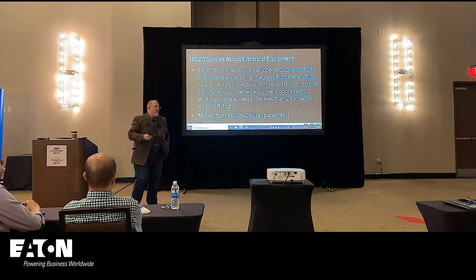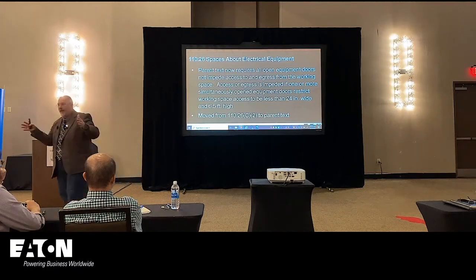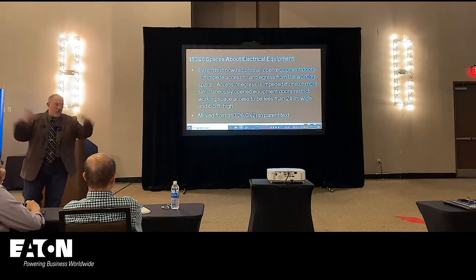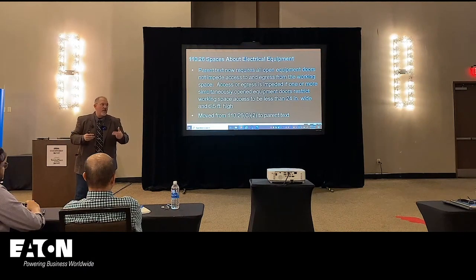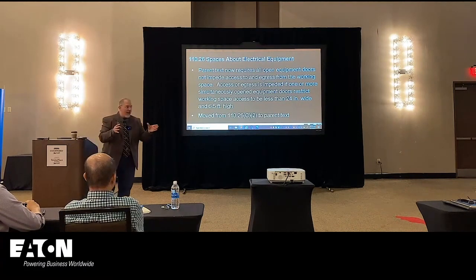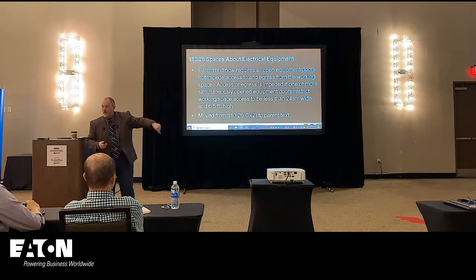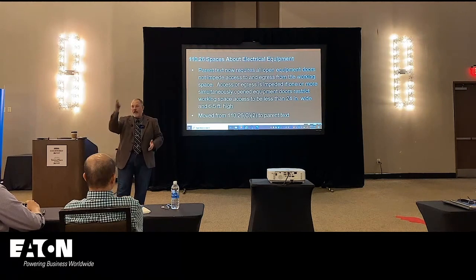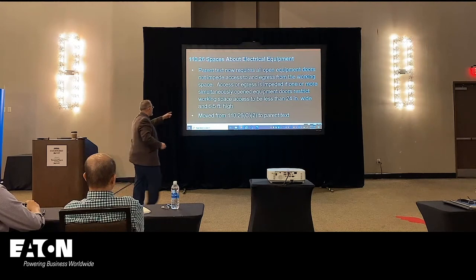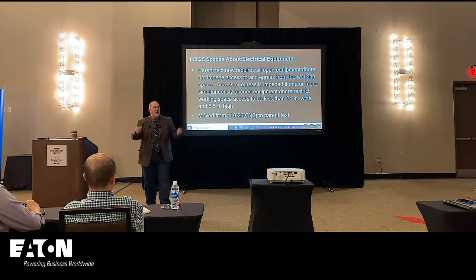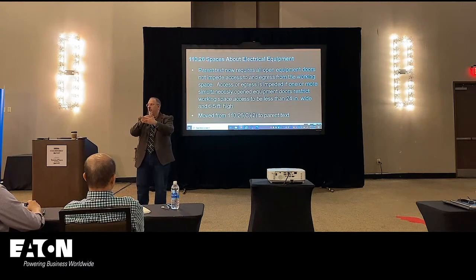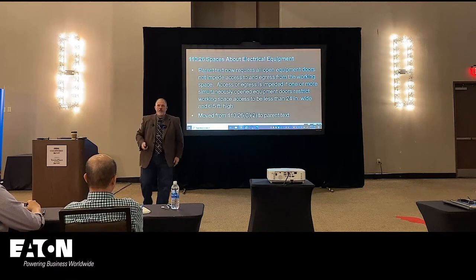All open doors. So remember, we took the large equipment. We made changes in large equipment. We said if it adds up to 1,200 amps and above, then you need to have two entrances and egresses from that room, not just 1,200 amps, right? So if it adds up to 1,200 amps. And we also added language that says open doors cannot impede egress to or from a working space. And what they did was they took that language and moved it to the parent text, both for low voltage and medium voltage. So now if you have a hallway and you have equipment on either side of that hallway, it says simultaneously open equipment doors. So if I open the doors on both sides of the hallway, I need at least 24 inches of egress space. If your hallway's short or your hallway's wide and your equipment is deep and you open both sets of doors and you don't have 24 inches, you have an issue with egress.